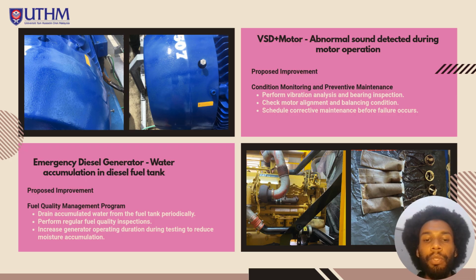For the generator, periodic water drainage and fuel quality inspection should be conducted. Longer generator operation periods during routine tests can also help reduce the moisture accumulation inside the fuel tank.